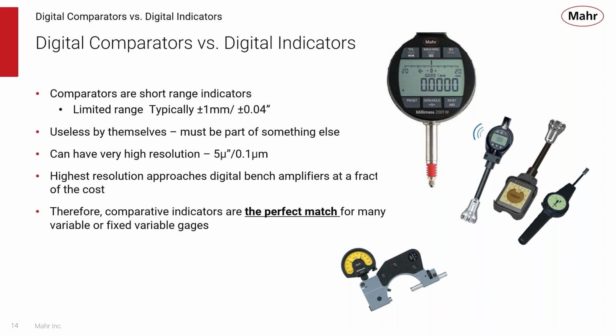Comparators, because they're using what's called an LVDT, or a linear variable differential transformer, are always comparing a known to an unknown on their internal standard. So what do I mean by that? Well, the way an LVDT works is you supply voltage to the LVDT, and then based upon where the rack is in its stroke, how far up your spindle has gone, that changes the voltage coming out. So what you're doing is comparing voltage coming into the LVDT versus voltage coming out of the LVDT.